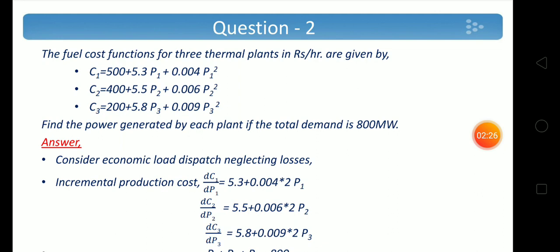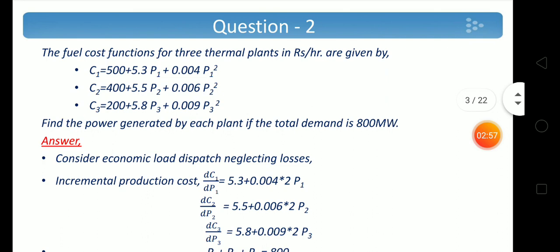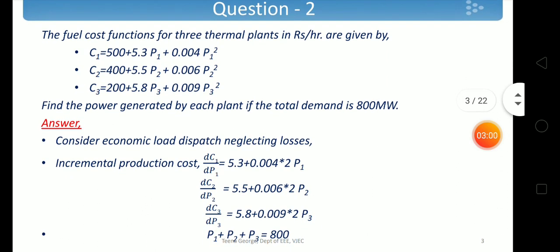The condition is incremental fuel cost should be equal and equal to lambda. We can find dC1/dP1 = 5.3 + 0.008·P1, since d(P1²)/dP1 = 2P1. Similarly, dC2/dP2 = 5.5 + 0.006·(2P2), and dC3/dP3 similarly. Also, it is given that power demand is 800 MW, which has to be met by 3 generating units: P1 + P2 + P3 = 800.